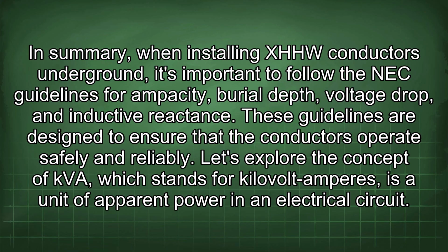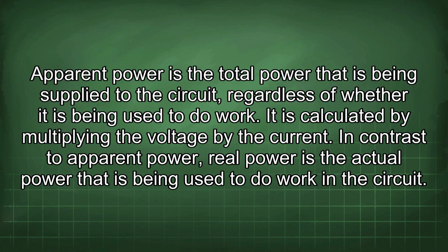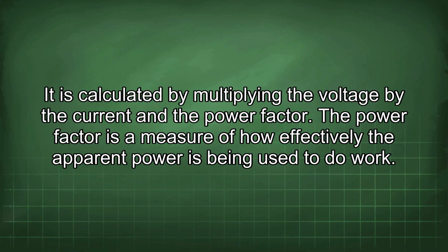Let's explore the concept of kVA, which stands for kilovolt amperes, a unit of apparent power in an electrical circuit. Apparent power is the total power that is being supplied to the circuit, regardless of whether it is being used to do work. It is calculated by multiplying the voltage by the current. In contrast to apparent power, real power is the actual power that is being used to do work in the circuit. It is calculated by multiplying the voltage by the current and the power factor. The power factor is a measure of how effectively the apparent power is being used to do work.